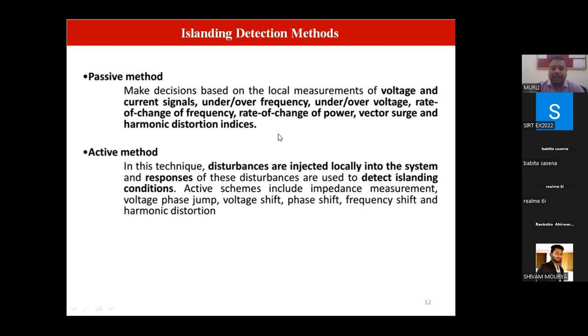So there are various methods of islanding detection. One is passive and one is active. Under the passive method, we can have local measurements like voltage and current signals, frequency measurements, rate of change of power, rate of change of frequency, like this. After measuring these parameters and processing them, we can devise an islanding detection method. While in the active method, some disturbances are injected, the responses against these disturbances are monitored, and through that we propose the islanding detection method. So those can be the two methods.